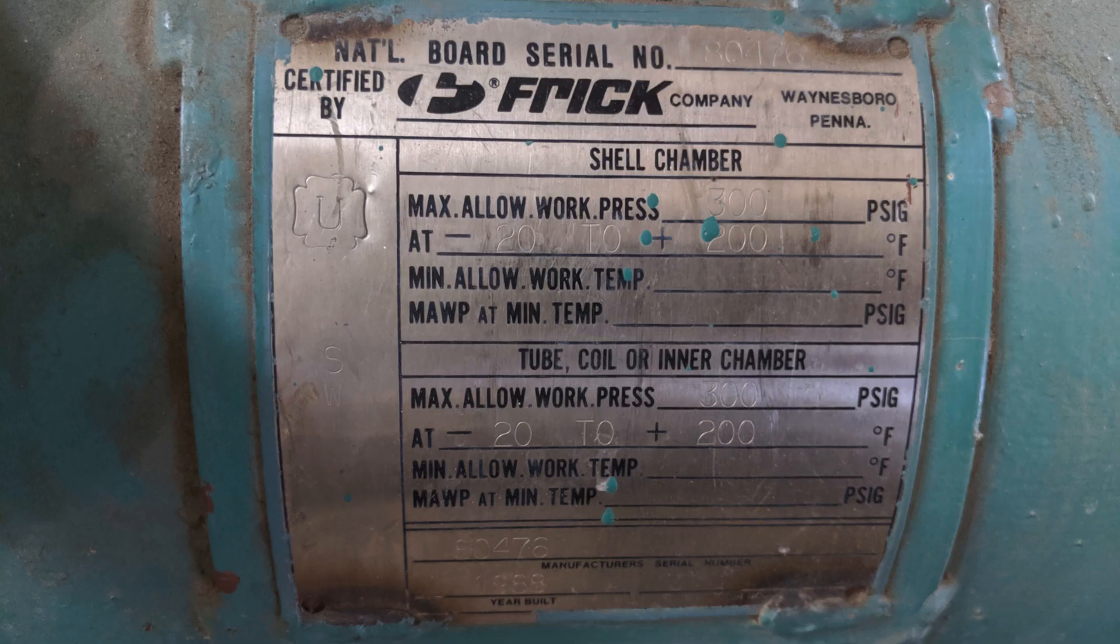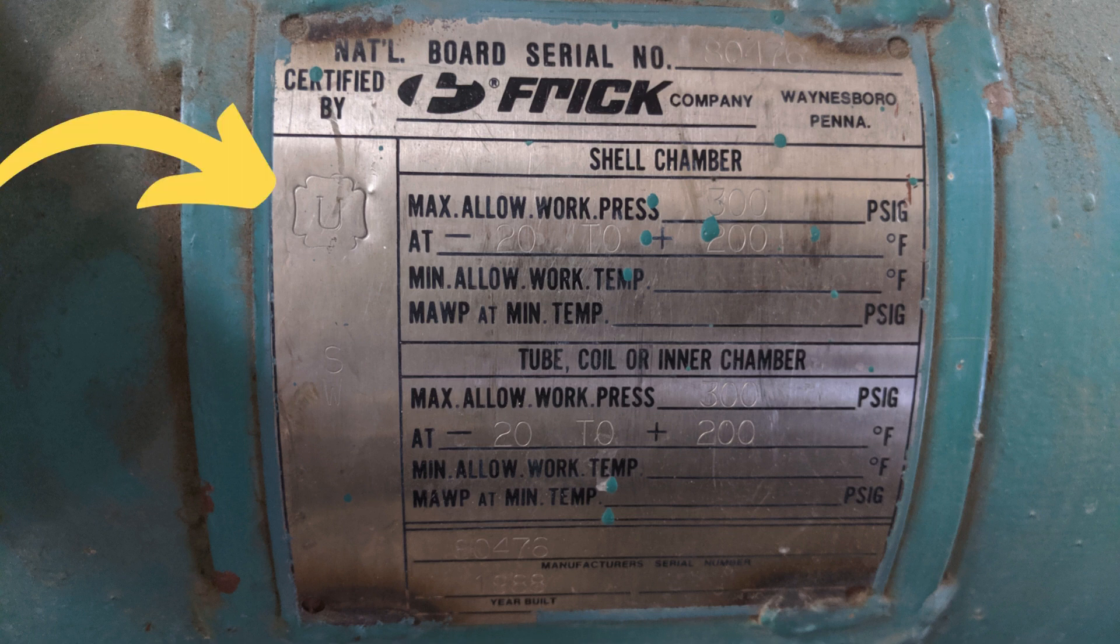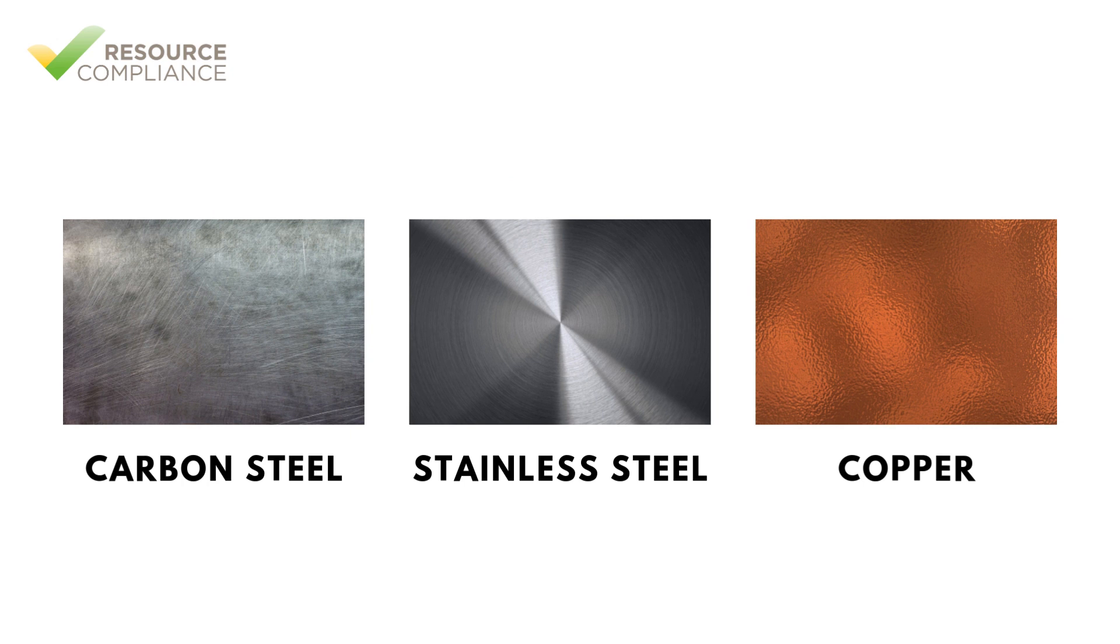Shell and tube condensers provide efficient heat transfer due to their large surface area. Furthermore, most shell and tube condensers are ASME stamped heat exchangers, making them durable for industrial applications. The tubes are typically constructed of carbon or stainless steel for ammonia systems.